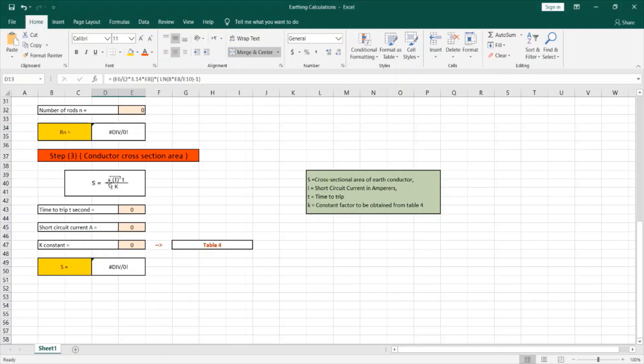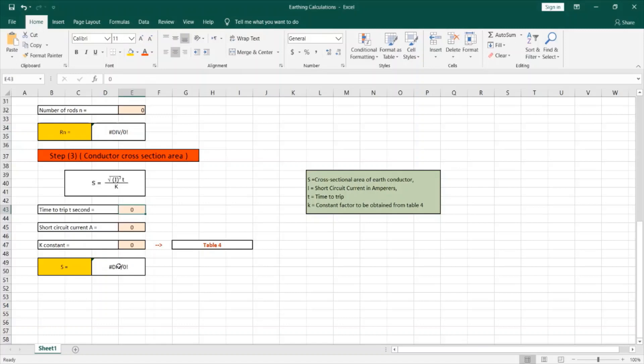To solve this equation we have to obtain the short circuit current value and enter it in this cell. We also enter the time to trip of the circuit breaker, which in most cases is one second. Finally, we obtain the K factor from an external table, and then the size of the conductor will be calculated at this cell in millimeters squared.